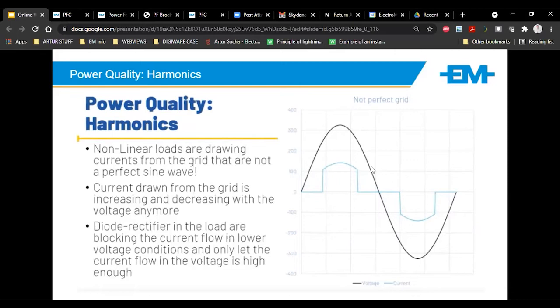So nonlinear loads, like a VSD, do not draw the current perfectly from the grid, so they will deform the waveform of the current. Why does this happen? A VSD only lets current flow depending on a voltage condition, and it will pulse. And as it pulses, it creates a new waveform, which I'll show you what it could look like.